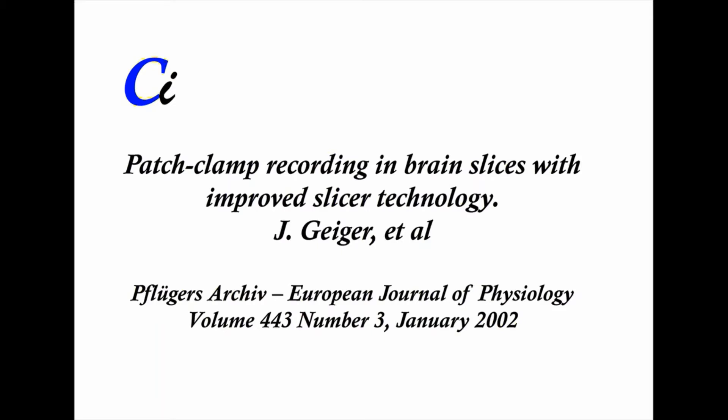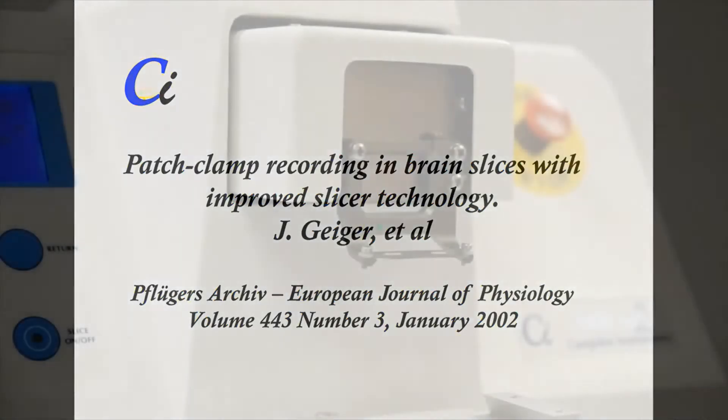Z-axis deflection refers to the vertical vibration of the blade during its lateral vibration. The vibrating mechanism of the 7000 SMZ Mark II slicer has been designed and assembled so that any z-axis deflection evident during its lateral vibration is restricted to less than 1 micron.